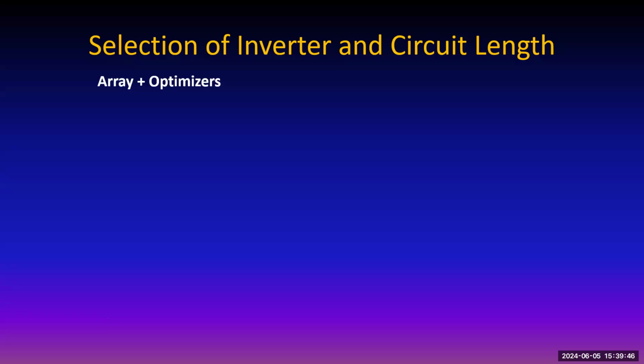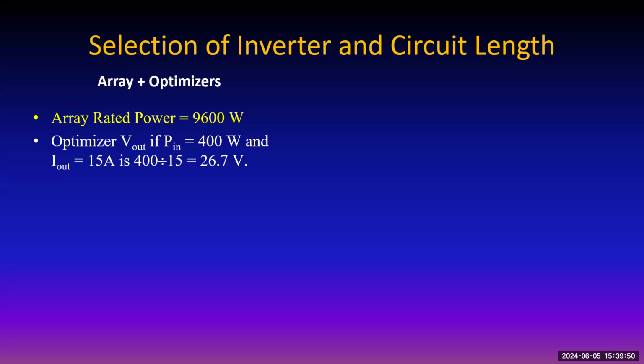Array plus optimizers. The array, we already know, is 9,600 watts. If the optimizer input power is 400 watts, and the output current is 15 amps, then the voltage is going to be 26.7 volts, simple. Voltage equals power divided by current. And the maximum current that optimizer is going to output is 15 amps.